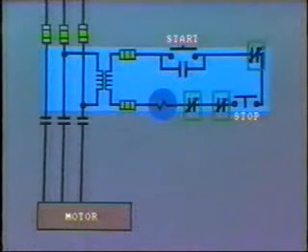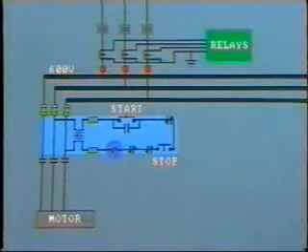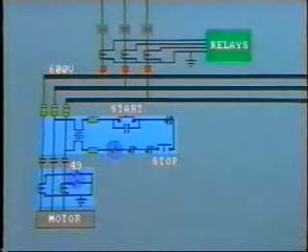Protective relays operate in the same manner, that is, by opening their contacts in the contactor coil circuit. So let's now add the protection devices. First, overload protection. CTs in the supply leads measure stator current, with the secondary feeding a thermal relay, number 49.